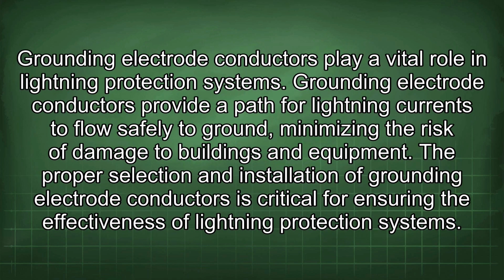Grounding electrode conductors play a vital role in lightning protection systems. Grounding electrode conductors provide a path for lightning currents to flow safely to ground, minimizing the risk of damage to buildings and equipment. The proper selection and installation of grounding electrode conductors is critical for ensuring the effectiveness of lightning protection systems.